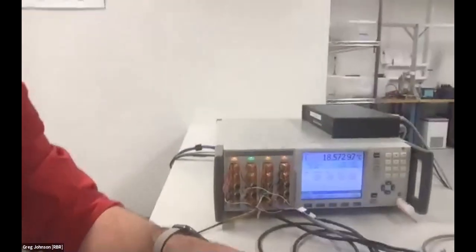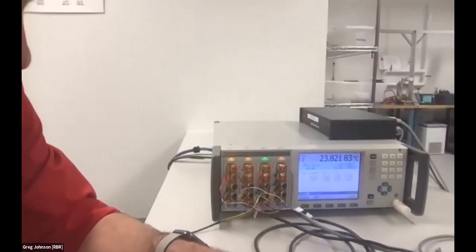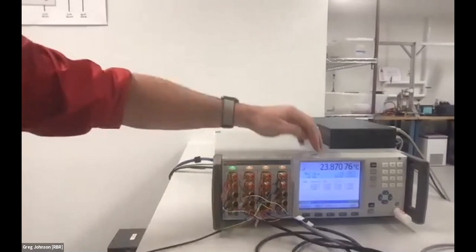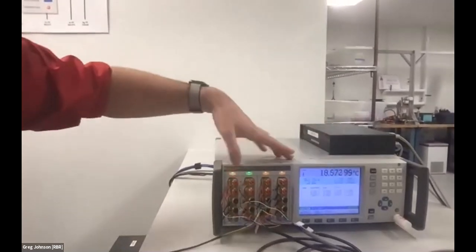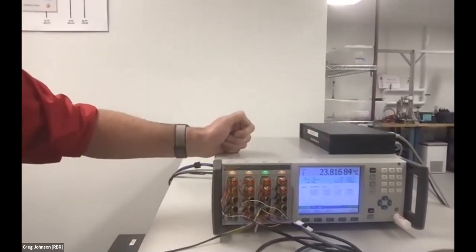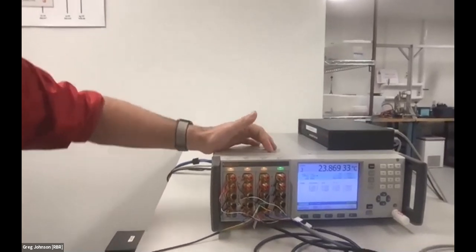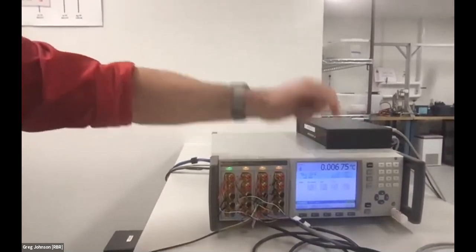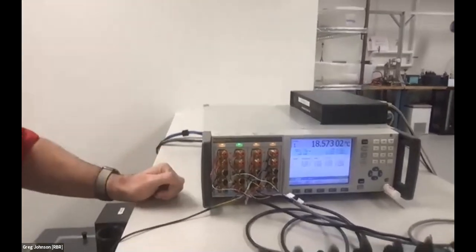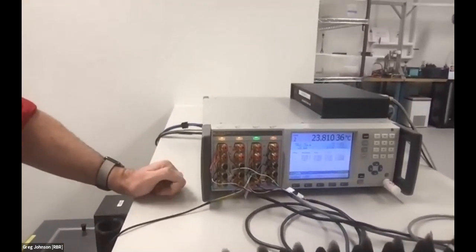To measure that, it's done in a resistance bridge. We have one here that I'll show you. This is a 4-channel so-called super thermometer resistance bridge. And these numbers are rotating through as each channel is being cycled. It takes about a second to make a measurement. And you can see that we're measuring to about 10 microdegrees. Our accuracy of the SPRTs, uncertainty is about 0.1 millikelvin.